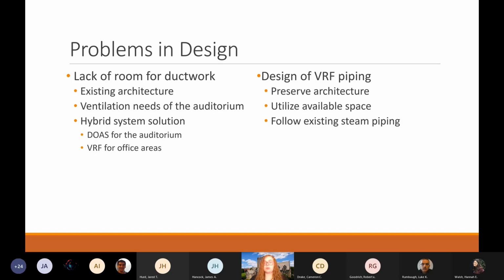The last design challenge we encountered was designing the piping and ductwork for the system. It was important to try to preserve the architecture of the building, so the piping and ductwork installation areas had to be generally accessible in order to limit the amount of damage done to the building during renovation. We worked to run our piping alongside the current steam heating piping wherever possible, so we could limit the number of areas where we would end up disturbing the architecture. Now I'll pass it off to Molly to talk about some recommendations.